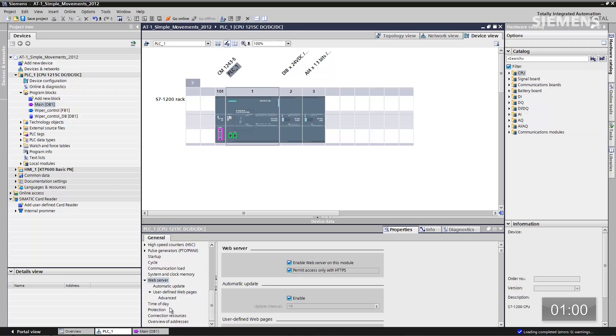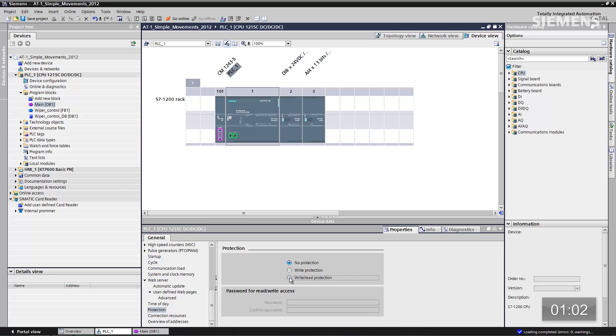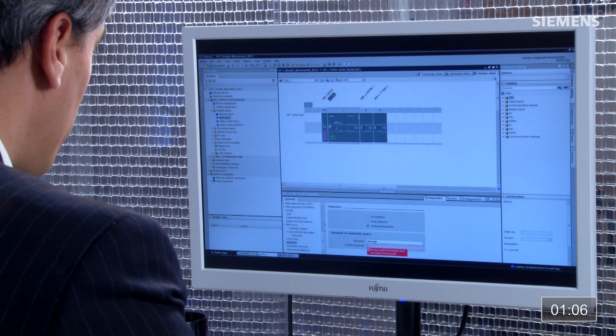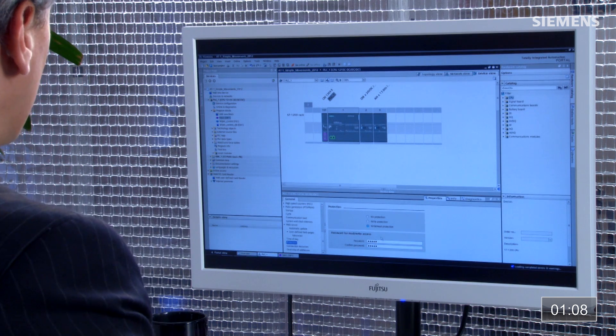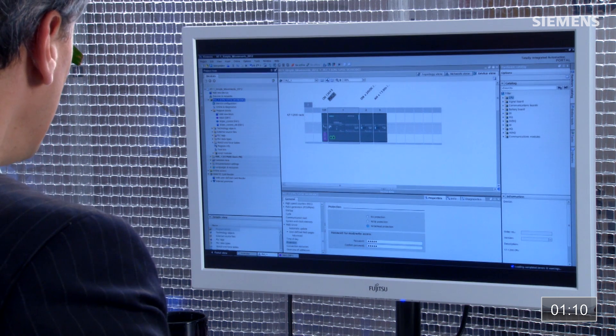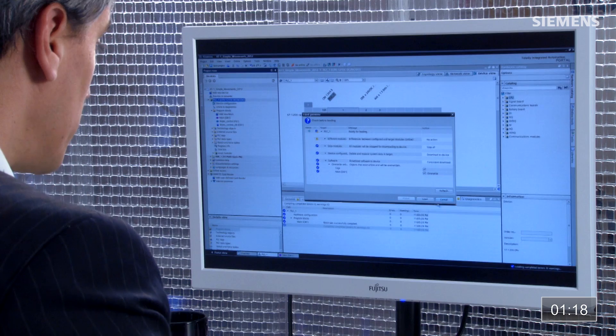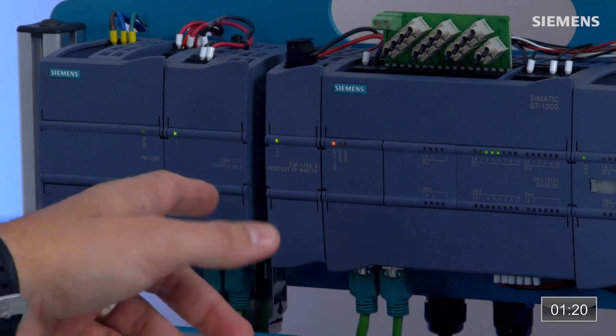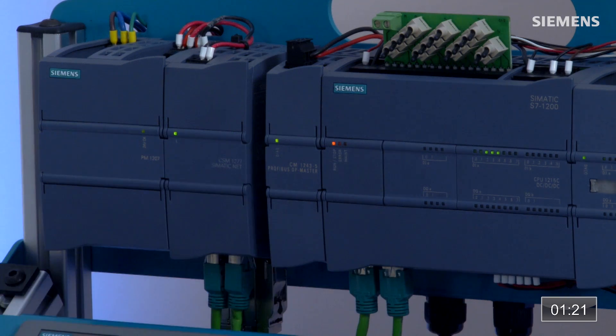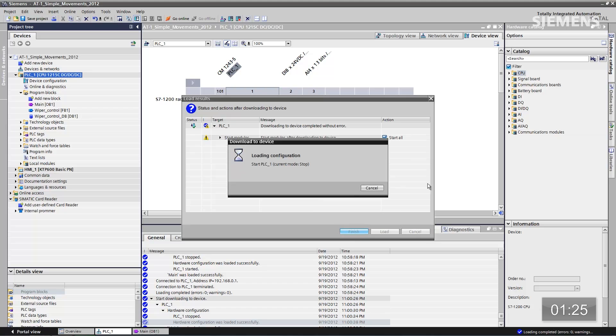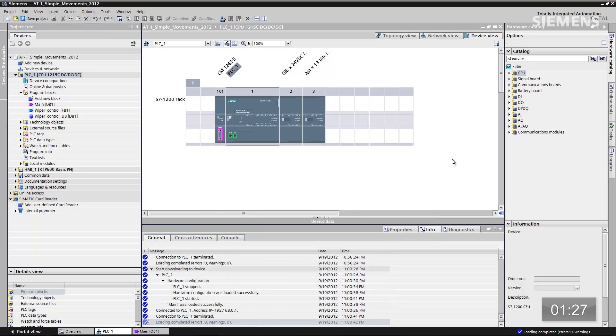Now go down to protection and click on read/write protection, and add a password of 'admin' — enter it once and twice. Now give focus to the CPU and click the download arrow button. It's going to compile the code changes we made: we added password protection as well as the web server. Click on load. Now you can see we are loading to the control system. Once finished, click on it — we are now done and have a completed system with the changes.